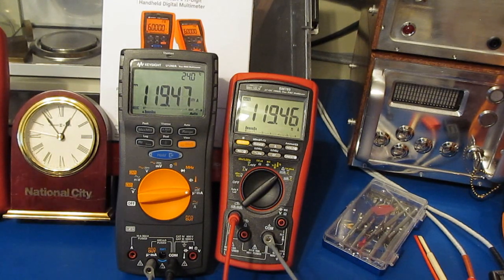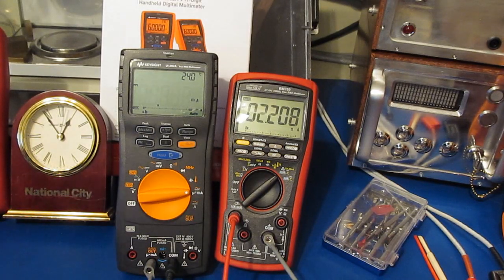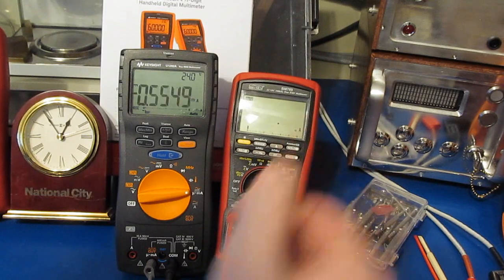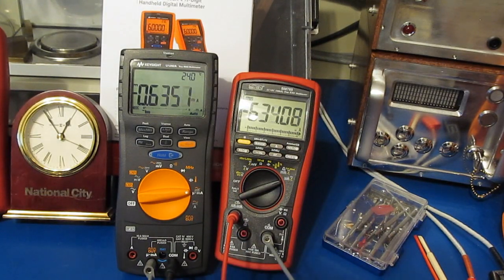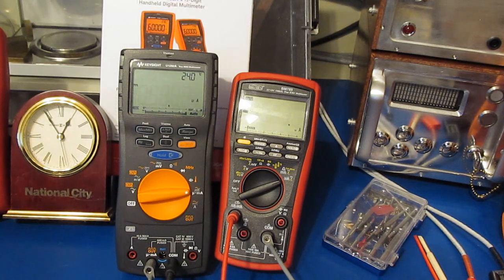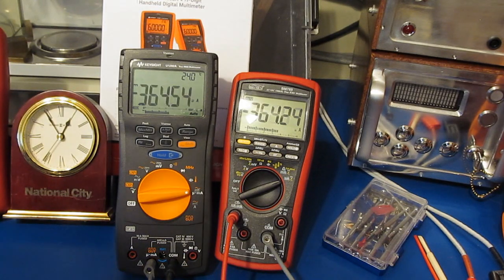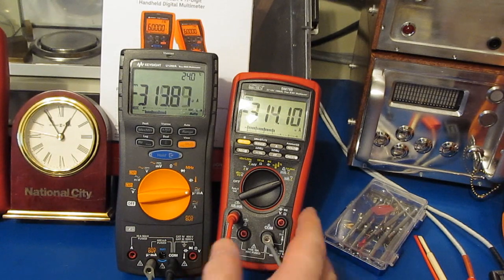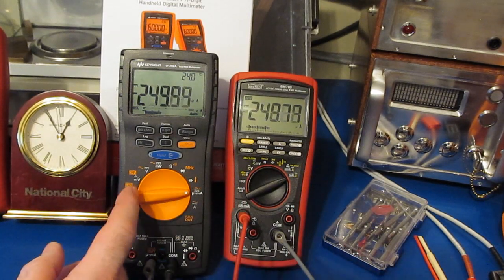Again, this meter takes a little while to respond. You can see both basically reading the same value. We can go up a little bit higher. Looks fine. If you'd like to see microamps, we'll turn this down a little bit and change this over to the microamp range. Again, you can see both meters reading basically the same value. Let's try adjusting this down a little bit, to get into a lower range. Of course, my power supply isn't very stable down here, but again, you can see both meters basically reading the same value. So it doesn't look like we've damaged the Keysight meter from this 2 kV test.